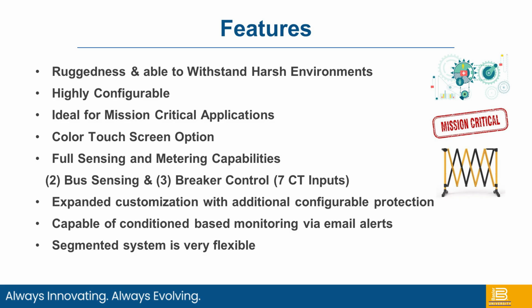The one thing that is an advantage to the HD is we have the capability of having 2 separate bus sensing and being able to control 3 breakers. It's definitely a thing that leads us in the industry. So not only the ruggedness, but also the ability to have 3 circuit breakers being controlled at the same time.